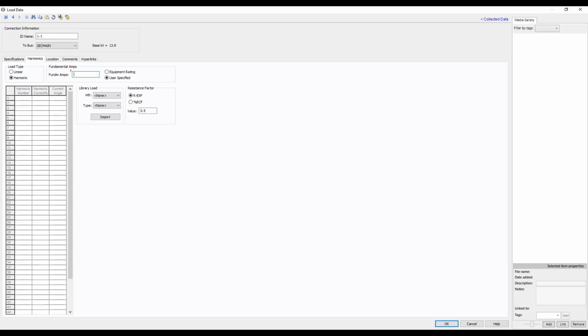So if it's a VFD drive, you need to have the harmonic current values, and often I just put in 100 amps there because this is looking for percent, and then from there I can put in the actual harmonic current. So it might be fifth harmonic. I might have 10 amps of fifth for that device, and then 3 amps of seventh, and so on. So you need to know harmonic number and harmonic current output, or harmonic percent. And if you put in fundamental amps here at this tab, you would put in the percent harmonics here for that device. If you know the amps, then put in 100 amps here and just put the value of amps there. And that's the typical way that I model harmonics, is actually real current injection for those devices.